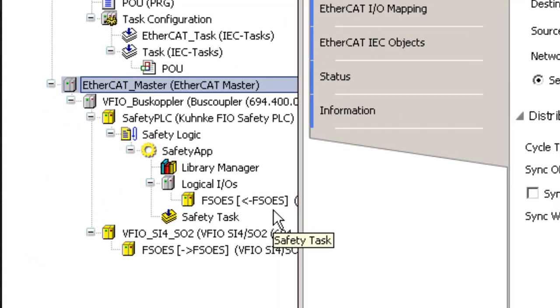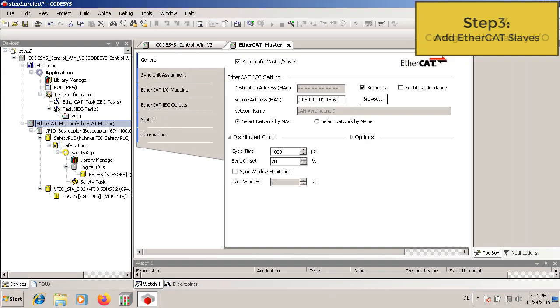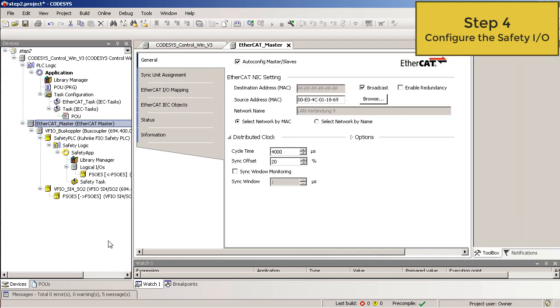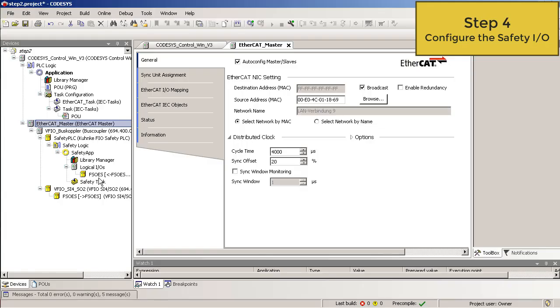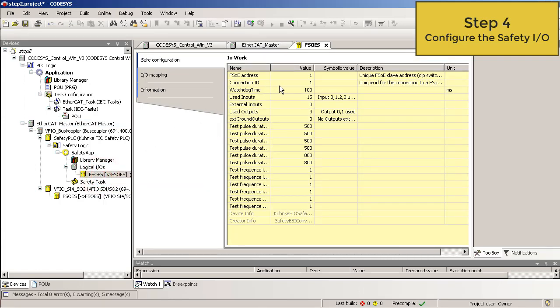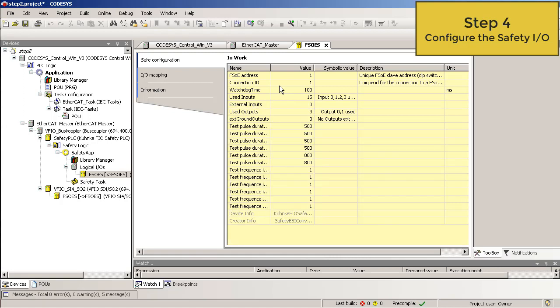Now a safety application with all safety devices is inserted. In the next step, I show you how to configure the safety I/O. Step 4. Configure the safety I/O. As you can see, the safety I/O is also inserted as a logical I/O. Double click on the safety I/O. And in this tree, you have to set the unique FSOE address. This address must match with the address which is set with the DIP switches on the left side of the safety I/O.